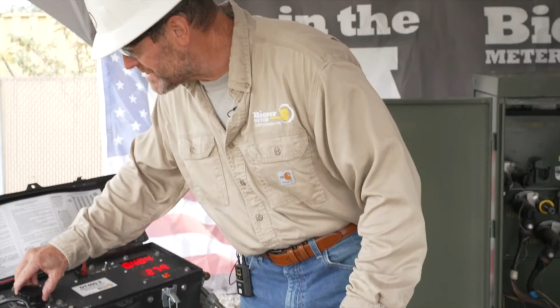All right, and we're going to come down. It requires 165 amps. We're going to bring this variac down to 165. It's a beautiful day in South Carolina, so it's not too hot. We're in the shade, in a kind of controlled environment. You don't want to do this in the sun. It feels nice out here, actually. All right, and we've got 165 amps. We look at the voltage drop, 0.22. So the chart, if it's 0.24 or less, it passes. So this passes. It's good.